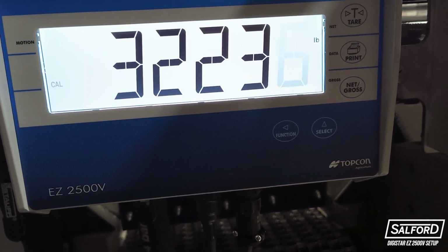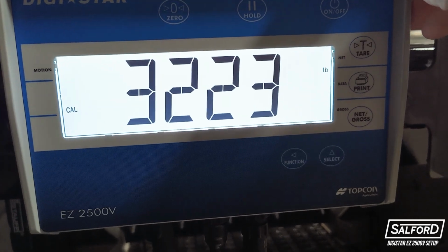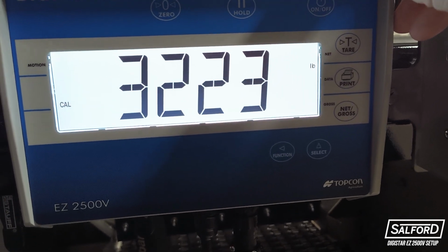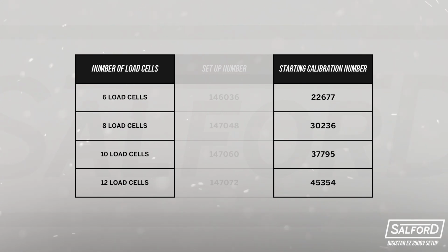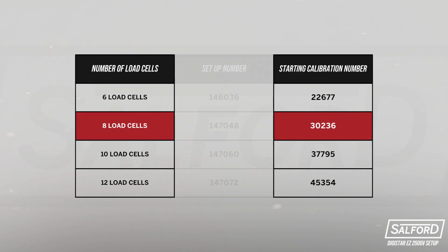Next, the starting calibration number will be entered. This number will be changed during the calibration process, but the initial value will be based off the number of load cells as displayed on the screen. Again, in this example, we are using 8 load cells, and therefore the starting calibration number will be 30236.